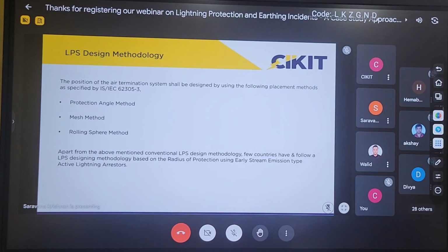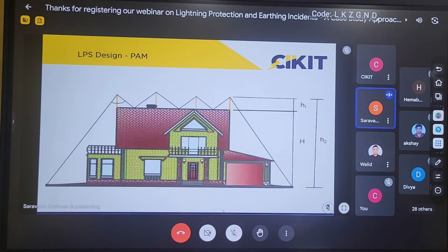So, this is the protection angle method. From the name itself, we can observe that the protection mainly depends upon the angle. If you closely observe, the angle depends upon the level and the height of the air terminal. If we observe the angle on two sides of this air terminal at the corner, you can see that the angle is different on both sides, because the angle depends upon the height above the reference plane.